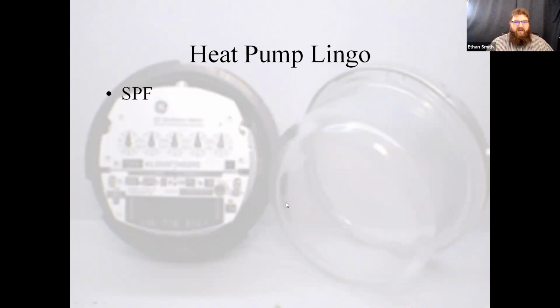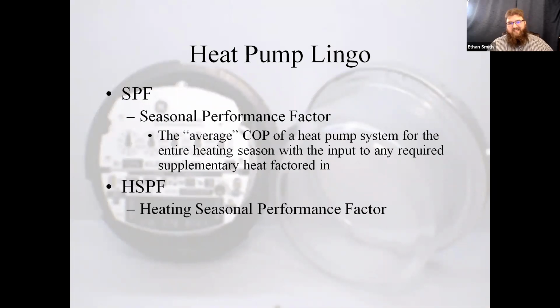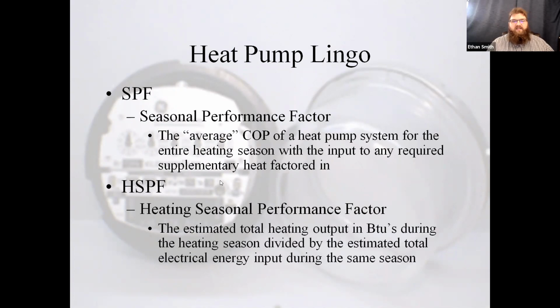Okay. SPF is our seasonal performance factor. We don't use this a whole lot anymore. It used to be a big number that we saw a lot, and it's just the average COP of a heat pump for an entire heating season. But it also takes into effect any supplementary heat that you're going to need. HSPF is just heating season performance factor. It's a little more specific. We do see this used these days more, and it's the same thing. It's just over the heating season.